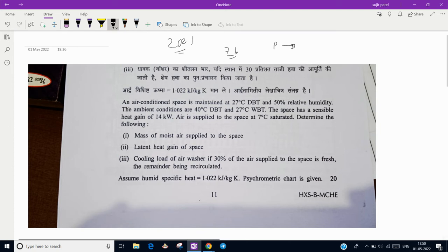Let's start. An air conditioned space is maintained at 27 degrees Celsius DBT and 50% relative humidity. That is the inside condition. The ambient condition is 40 degrees Celsius DBT and 27 degrees Celsius wet bulb temperature. This is the outside condition. The space has a sensible heat gain of 14 kilowatt. Air is supplied to the space at 7 degrees Celsius saturated. So this is condition number 2.